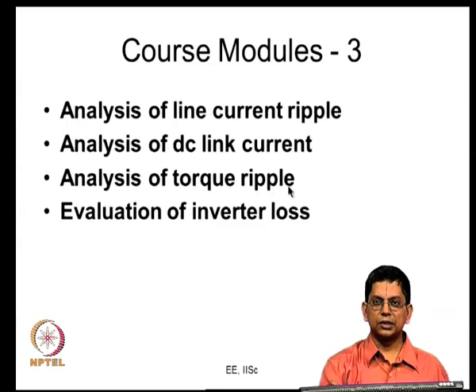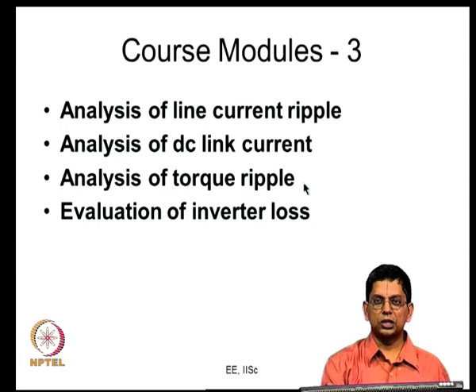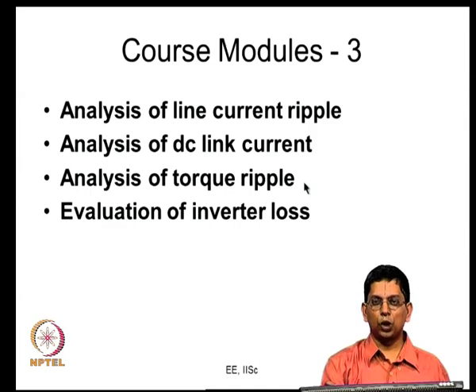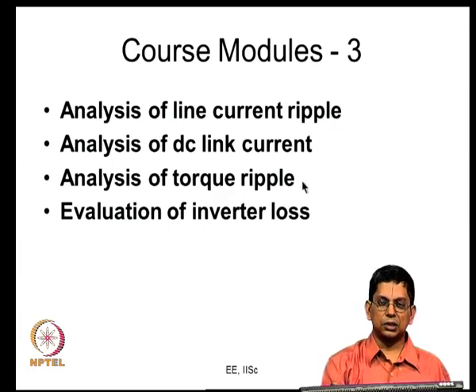We also considered the analysis part for the two-level inverter: how to calculate the RMS current ripple, how to calculate the DC link current, and some ways of estimating ripple torque. When running an induction motor from sinusoidal voltage there is only a steady torque, but when fed from an inverter there are harmonic components that result in harmonic fluxes and currents that produce pulsating torque.